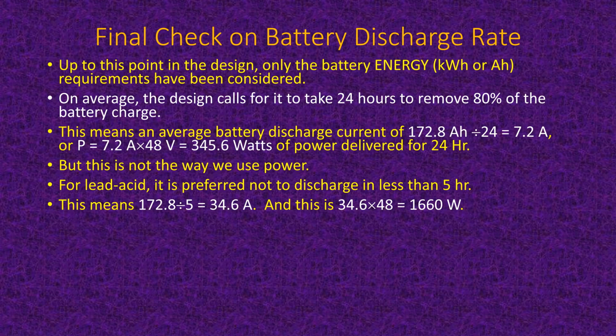Anything on a 20 amp circuit, you can do 1,660 watts, because the 20 amp circuit is just about that. 16 amps at 120 volts is a little bit more than 1,660. But in any case, it means that without making your batteries too unhappy, you can draw up to 1,660 watts. And most of the battery packs do have a power rating that they do not want you to pull more than a certain amount of power out of any particular battery pack. And that's one of the things you look at when you look at the specifications of the battery pack.